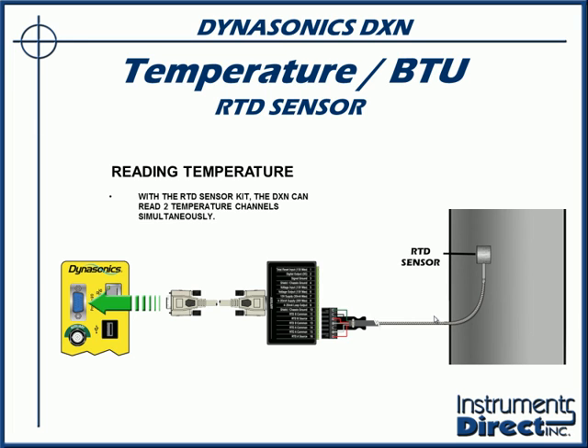So this device can monitor a whole host of applications. And just to recap, we're monitoring transit time flow, we're monitoring Doppler flow, we're monitoring the combination of the two, a hybrid application. And if you have them all interconnected, it usually defaults to the transit time. As long as the transit time flow meter is working, the Doppler turns off, and so on. And in addition to that, if you want to do an energy management application, you can add the optional temperature kits to monitor for BTU as well.